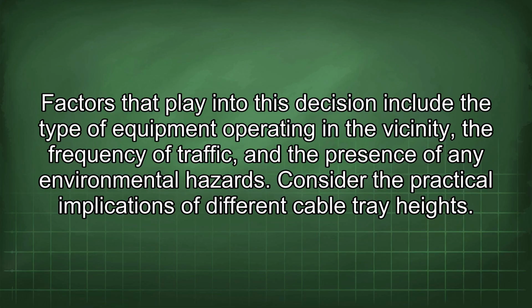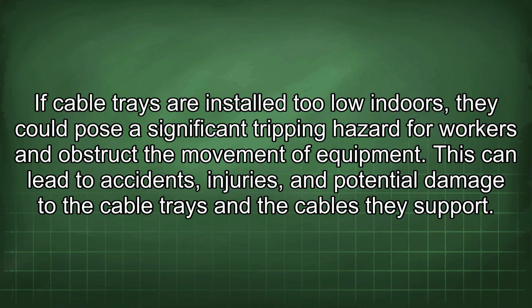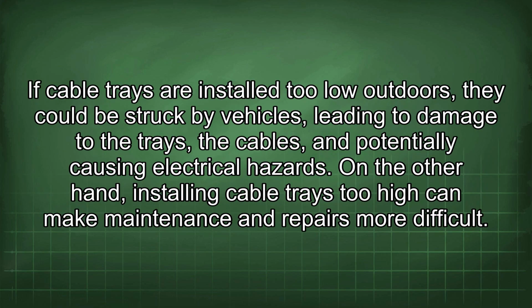Consider the practical implications of different cable tray heights. If cable trays are installed too low indoors, they could pose a significant tripping hazard for workers and obstruct the movement of equipment. This can lead to accidents, injuries, and potential damage to the cable trays and the cables they support. If cable trays are installed too low outdoors, they could be struck by vehicles, leading to damage to the trays, the cables, and potentially causing electrical hazards.